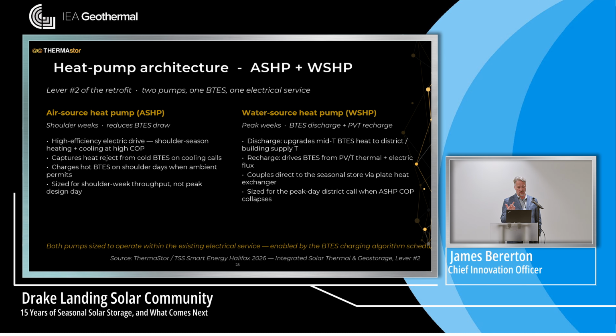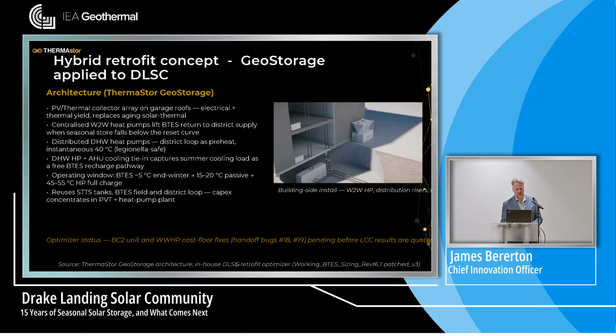So we use a combination heat pump. So we do a combination air source and water source. And what that does is it allows us to eliminate having two pieces of equipment. We double it up. We use the air source heat pump to meet the load directly. Typically we size for about 55% of the heating load to be covered by the air source heat pump. And the rest we're going to pick up when the air source heat pump is inefficient when it's cold outside, or it's inoperable because it's really cold. We live in Canada. So there are times when you can't use the air source heat pump at all. That's when we use the ground source and use the storage. So the storage will cover somewhere between 30 and 40% of your load in an optimal system.